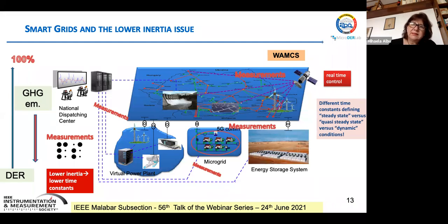The main result, governing everything we speak about after this, is that there is much lower inertia available in the system because we don't have the rotating mass of the large traditional generators. This means that if we want to control such a system, and this control can be done on a larger scale by wide area measurement and control systems, we need time constants in the control comparable with the time constants now describing the phenomena.